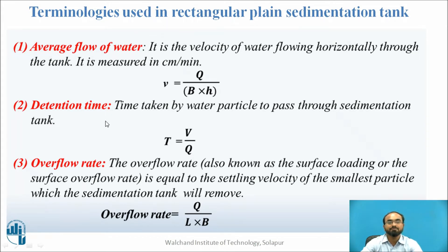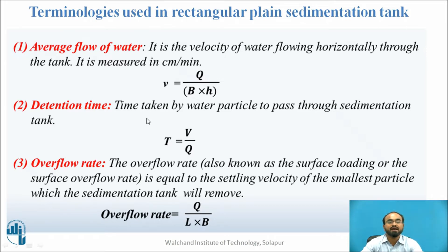What is detention time? It is the time taken by a water particle to pass through the sedimentation tank — the time required for water to remain in the tank. It is defined as capital T, with the formula T equals capital V (volume of tank) divided by capital Q (discharge of water).